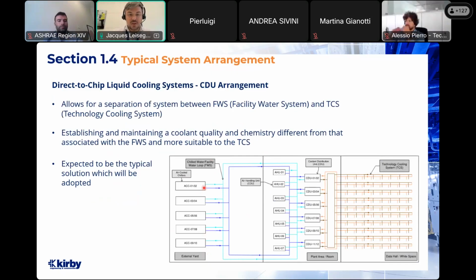So you have your heat rejection equipment, and then you may have a separate plant area or plant space internally where you have AHUs or fan wall units that can account for your airside load. And then you have a piece of equipment called a coolant distribution unit, or a CDU. Your CDU hydraulically separates your facility water loop from your technology coolant system. Your technology coolant system is the system which comes into direct contact with the cold plates on your server.